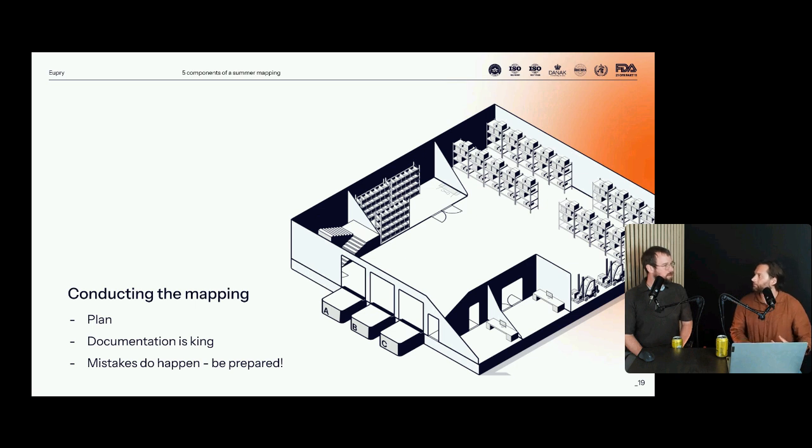So what are the most common errors or kind of those anomalies that you see? What are they caused by, usually? Oh, that's a really good question. When we're talking new buildings, it's often that we see people adjusting the HVAC system because they were not aligned that now we're testing, or equipment that's being turned off, or doors that have been opened. Sort of the normal work you would see with people entering and leaving.